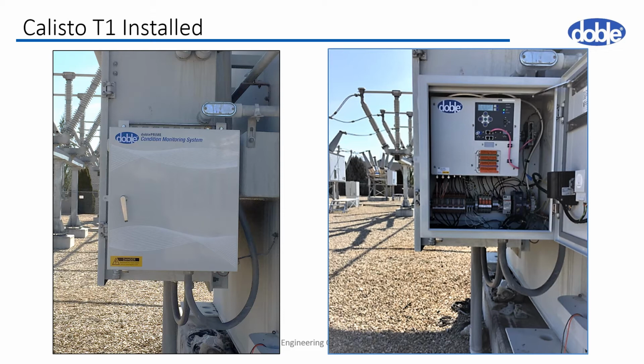When the unit is received from Doble, all of the terminal blocks are wired from the top of the terminal blocks to the T1, and all the power supplies, the network switches, the climate control, which is on the door that's on the right-hand side, are all there. One of the conduits, the conduit coming from the control cabinet to the T1, is for power. One of the conduits that drops down, it's a 2-inch conduit, is from the bushing tap adapters, and the 4-inch conduit coming out of the ground is from the CCVTs for the voltage reference.